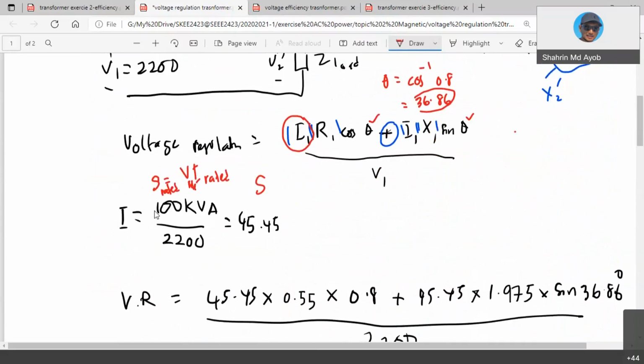S rated is equal to V rated multiplied with I rated, which we also call full load. Right now your S rated is 100 kVA, and your V rated is actually 2200. So you will obtain the values, only the magnitude, 45.45 amperes.